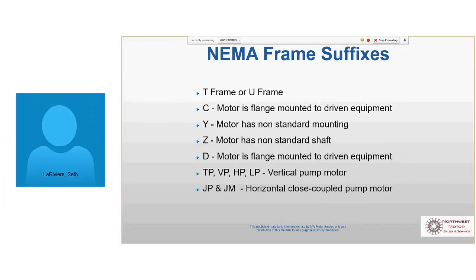I've seen some Ys that literally are round frame motor with no feet. So they're just mounted off the driven equipment. That wouldn't be a problem normally if I gave a guy a motor with feet. You just wouldn't use them, right? Well, sometimes that might be a problem if you've got a space limitation or something like that. So anytime there's a Y on there, I want to take a look at it.